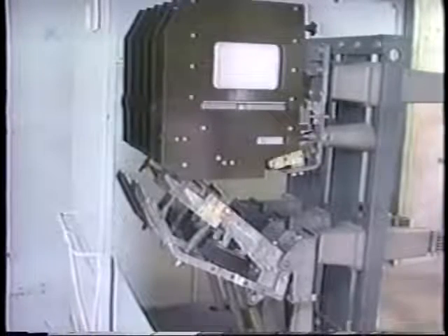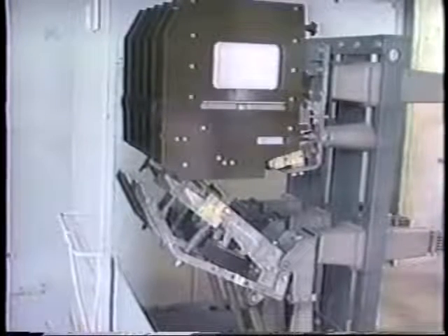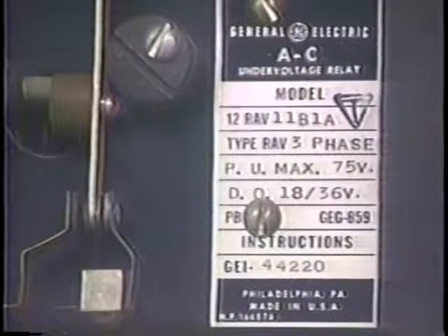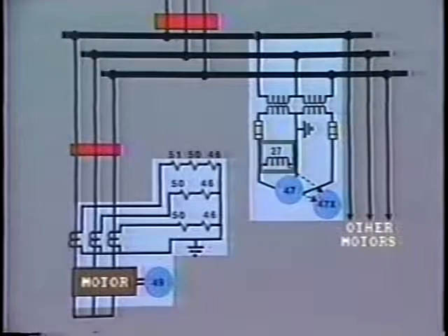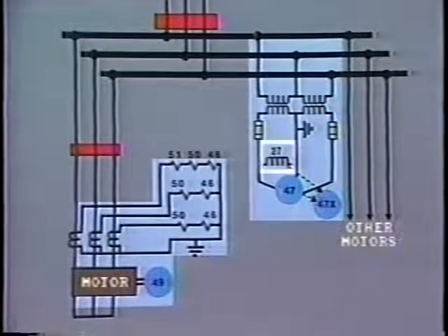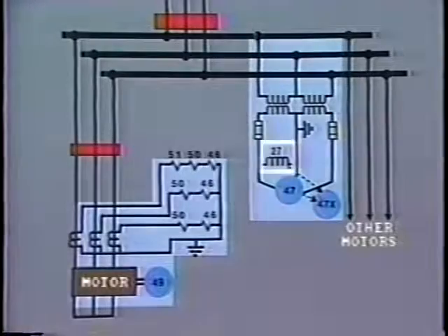Where circuit breakers provide direct on-line starting, undervoltage protection must be installed. This is because the circuit breaker will not open on loss of bus voltage. An undervoltage relay, 27, is connected to the bus. On loss of voltage, this will trip all the motor breakers on the bus, so preventing rapid reclosure while the units are running down. As we mentioned earlier, insulation failure usually leads to a stator ground fault.